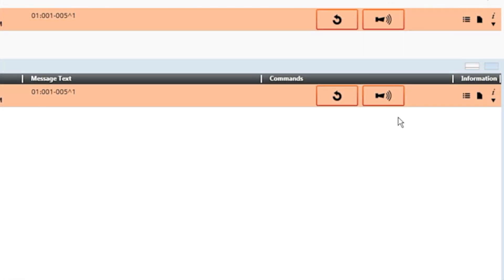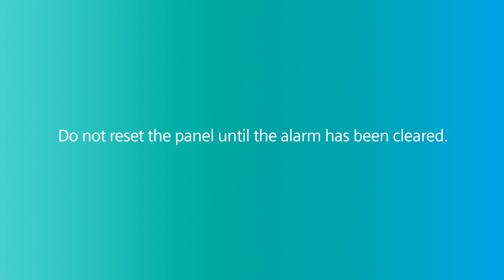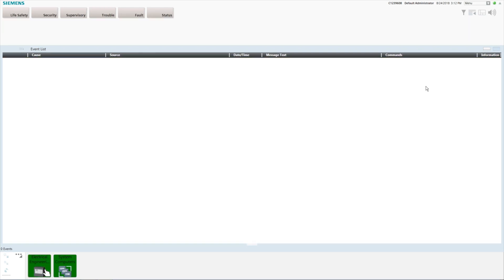To silence the notification appliance after evacuation where permitted, press the alarm silence button located in the commands column in the event list. The silenceable notification appliances will be silenced. As you silence the audibles, the next available command in the commands column changes from silence to the unsilence audibles command button. The reset button is also displayed. Do not reset the panel until the alarm has been cleared. When the alarm condition is corrected and when authorized, return the panel to normal standby operation by pressing the reset button.